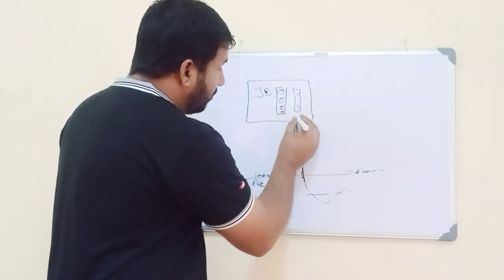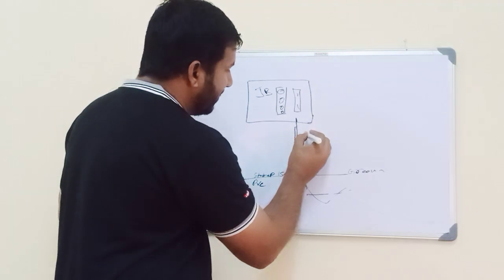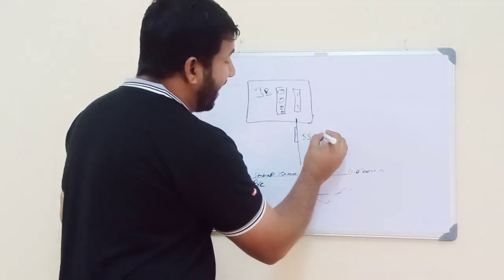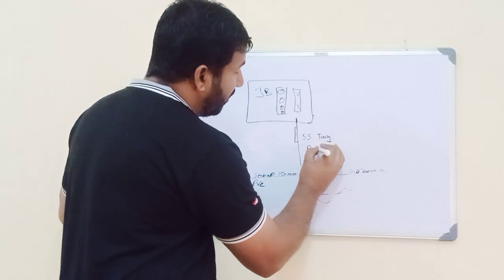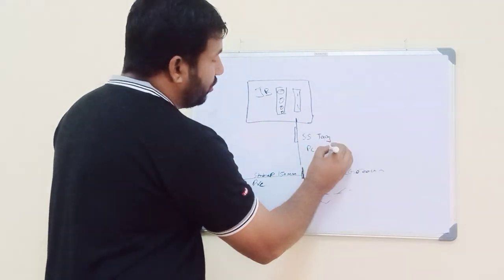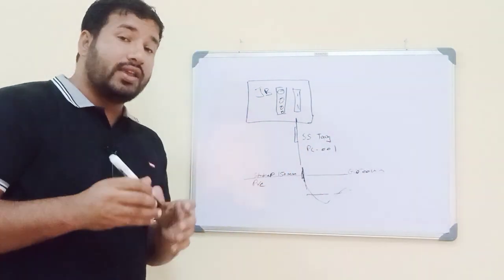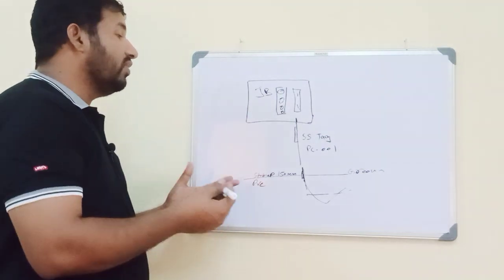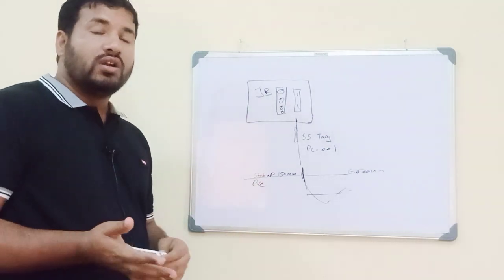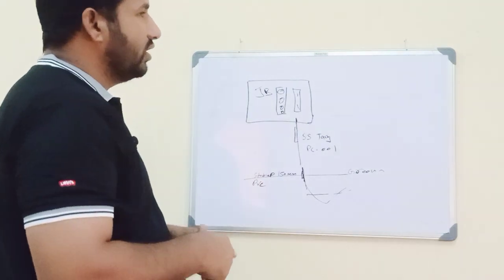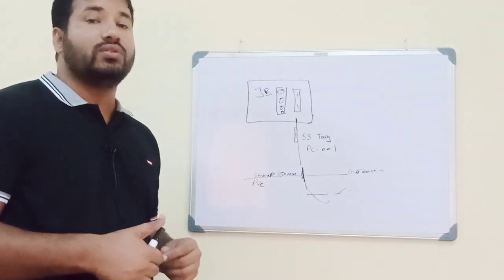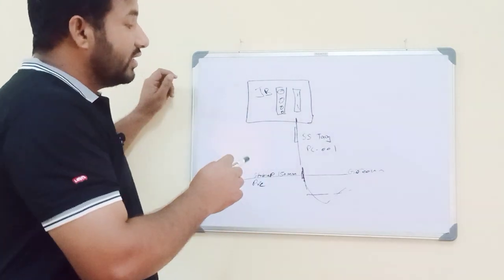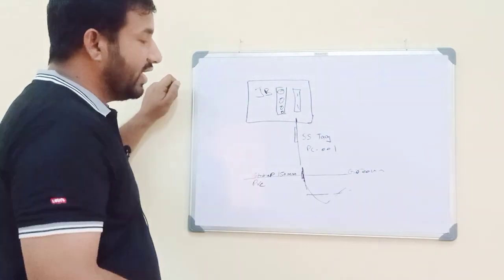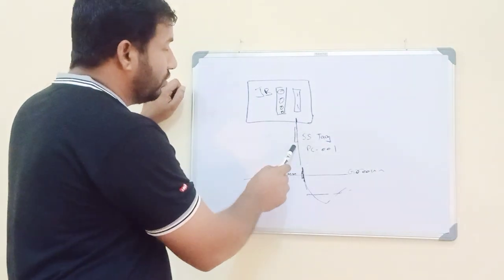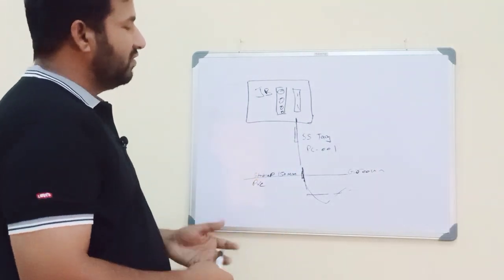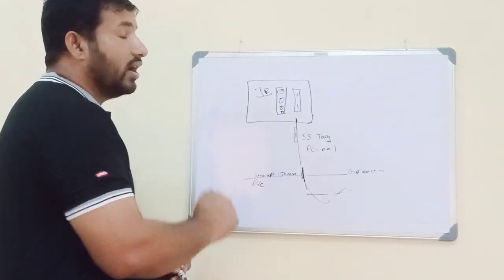So outside the junction box, we have here a stainless steel tag. Here is the cable number, suppose PC001 - there is only the cable number. Cable number means we can find that in the cable schedule. We will discuss in one more video related to drawings, what kind of drawings we use in electrical. So that cable schedule tag number, we have to put the SS cable tag with PVC coated steel ties, we have to use outside.